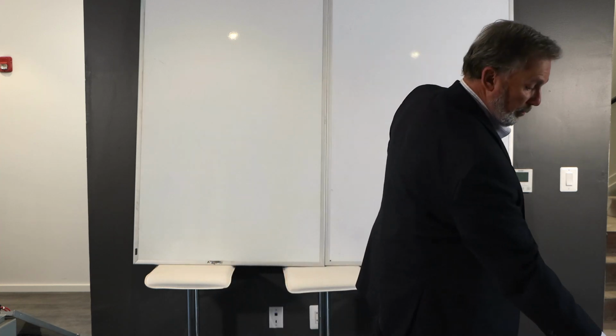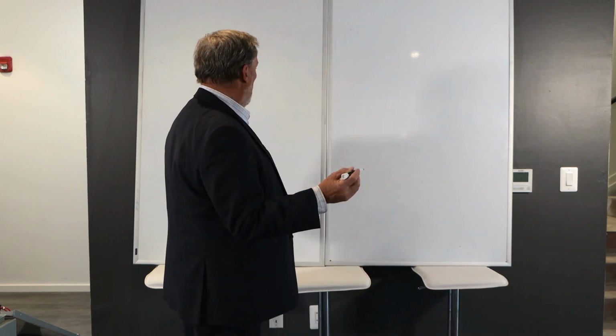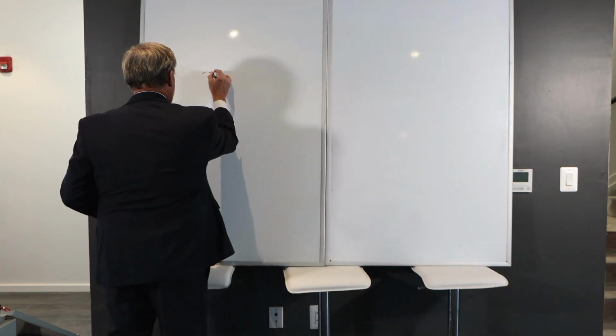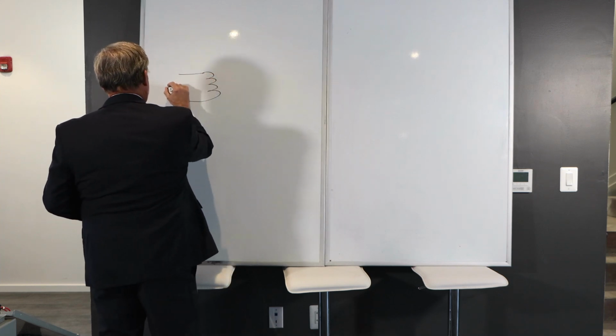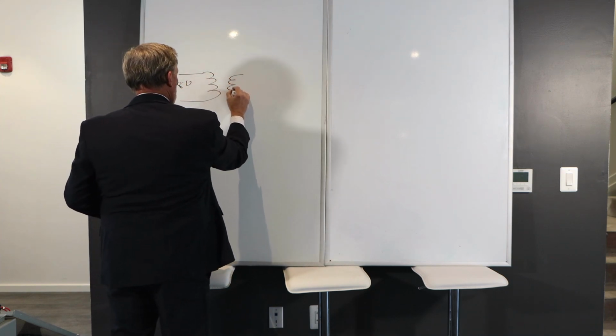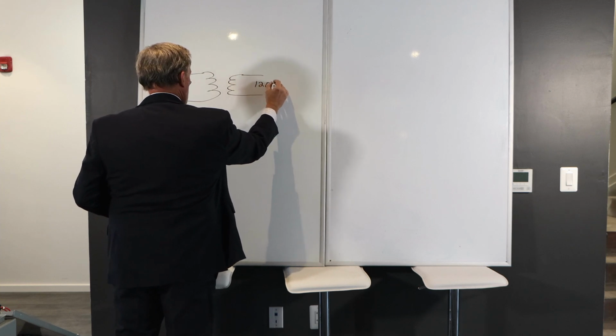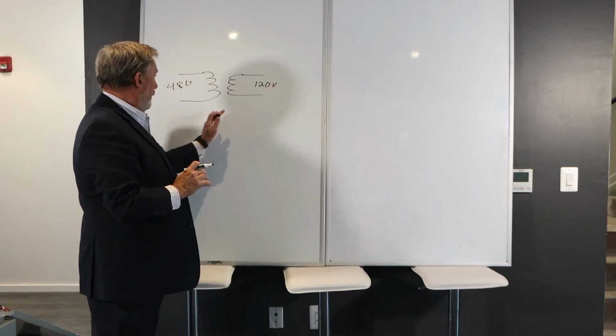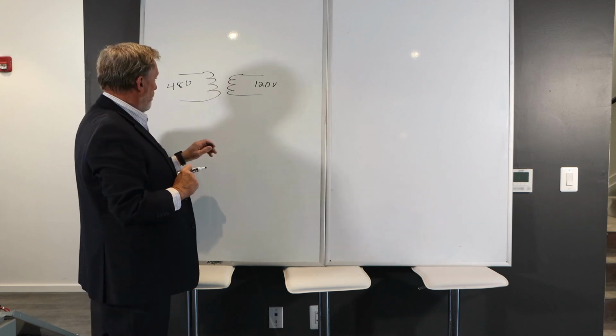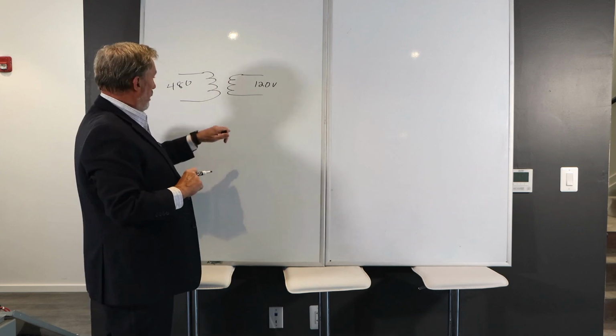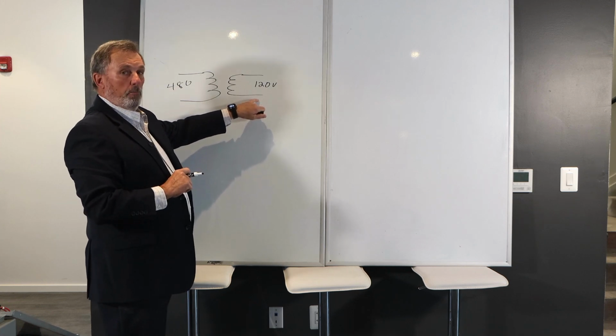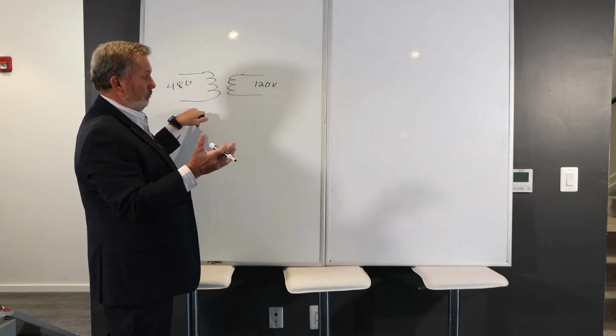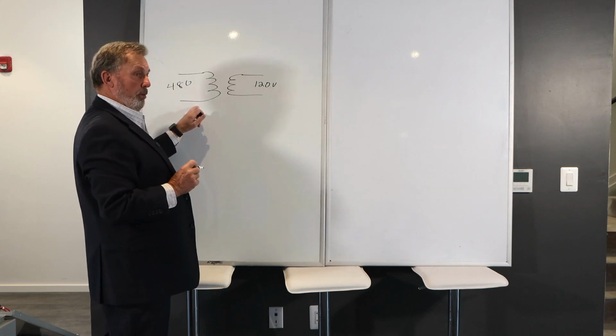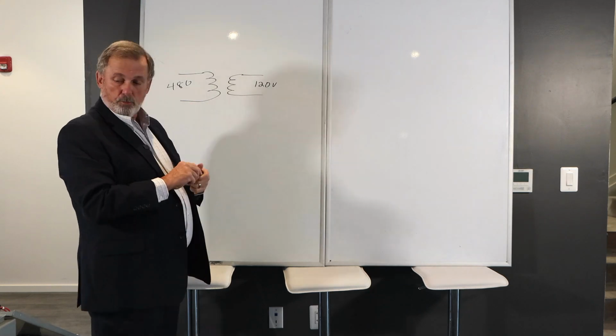But before we do that, I would like to go back to something we discussed previously, and that would be the actual control transformer. The control transformer has a primary of 480 volts, and the secondary is 120 volts. Now, a transformer is a strictly linear device. What I'm going to do for demonstration purposes is take an extension cord and put 120 volts on the secondary, and you're going to see a meter reading of 460, 480 volts on the primary, okay? So without further ado, let's give that a try.